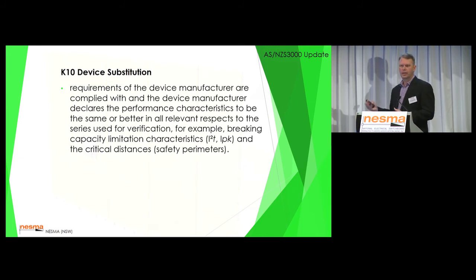But if you're going to change brands, it's very difficult to get one manufacturer to nominate that their product is going to be as good or better than whatever it was you tested. And that's where the trick is with device substitution. So what we're saying is, if you want to maintain full compliance with this document, you need to be very aware of just choosing who to put in the switchboard.